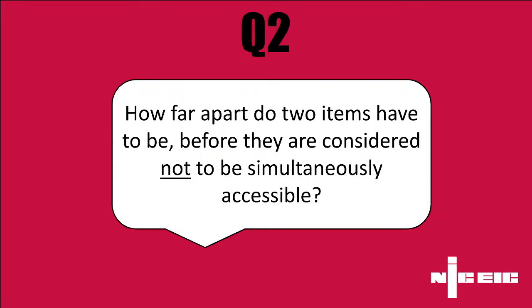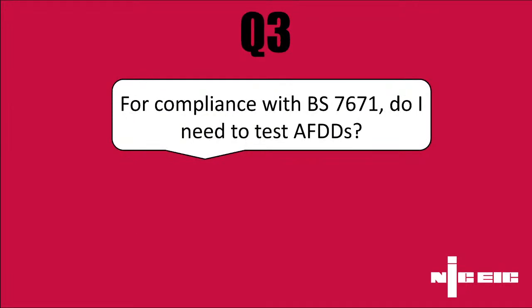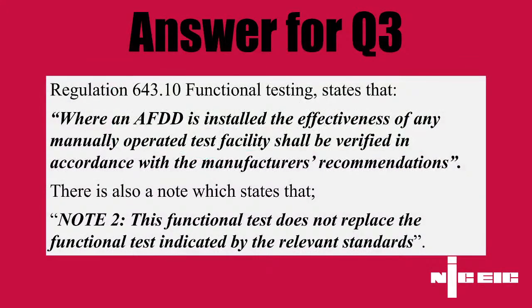Okay, another one: for compliance with 7671, do I need to test AFDDs? So functional testing, you'll find that under regulation 643.10. And where an AFDD is installed, the effectiveness of any manually operated test facility on that device shall be verified, but in accordance with the manufacturer's instructions. And again, talking about functional testing, that doesn't replace the functional test indicated by the relevant standards.